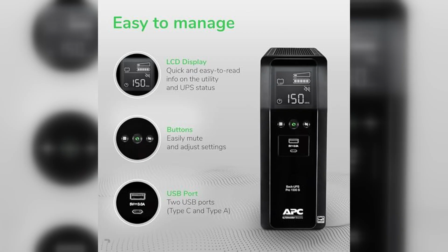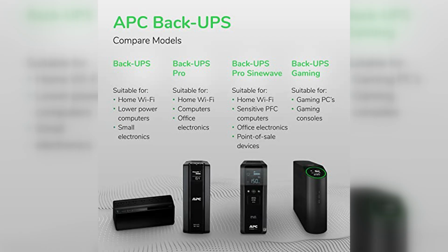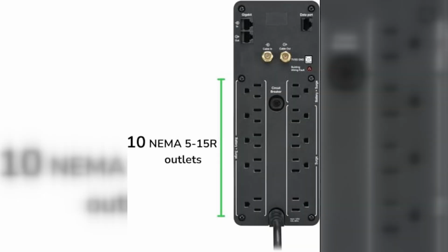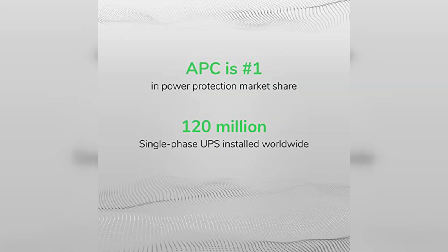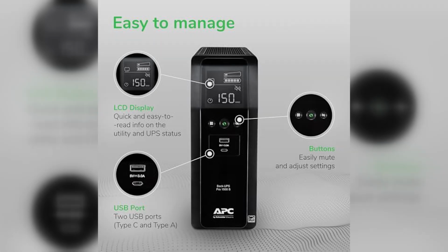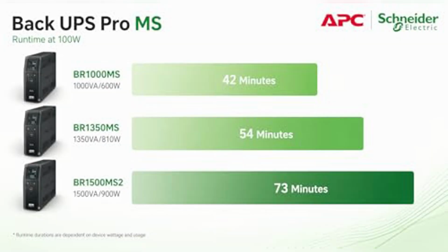Instead of constantly exhausting its internal battery cells every time the incoming wall voltage fluctuates, the automatic voltage regulation system uses an internal transformer to instantly boost low voltages or step down high voltages back to a perfectly stable, safe standard. This constant stabilization prevents subtle, slow degradation to your premium computer hardware components over time and keeps your internal batteries fully charged and perfectly fresh for when a total blackout actually occurs.